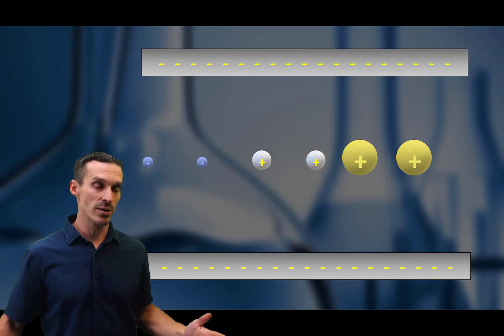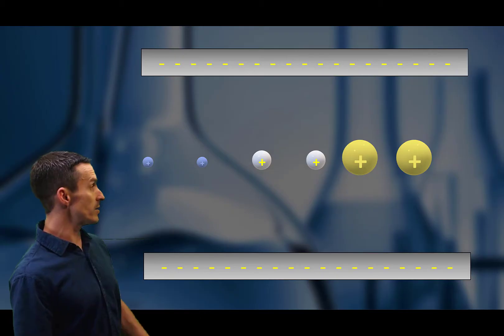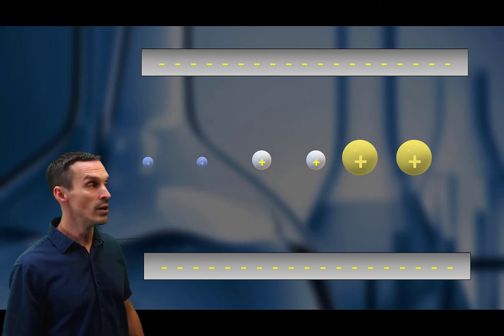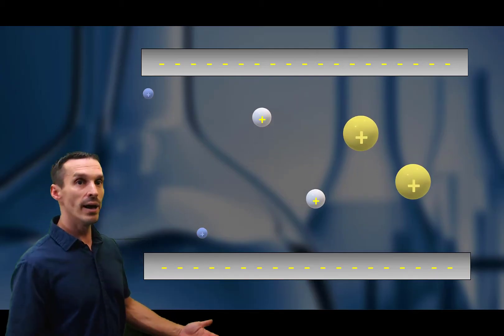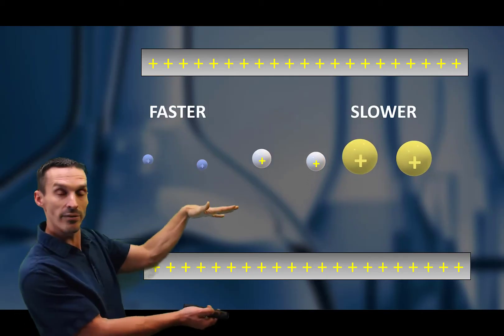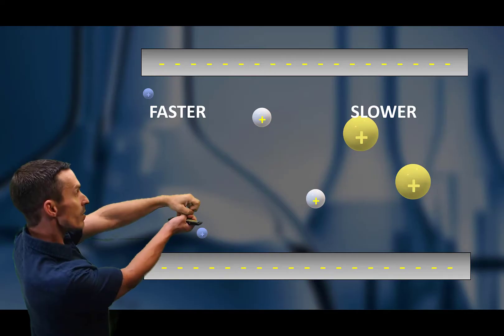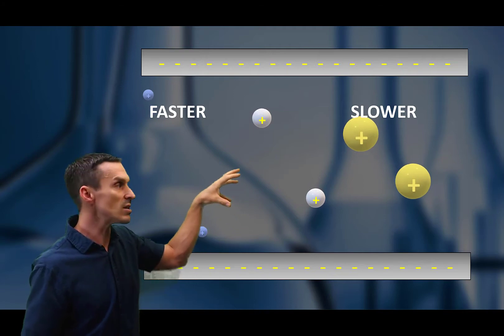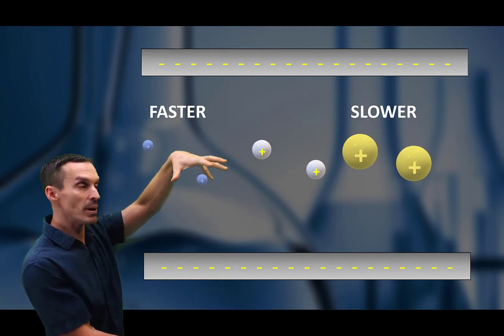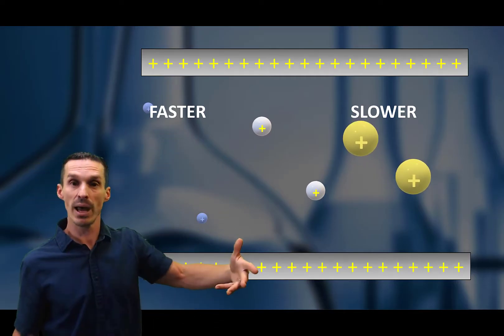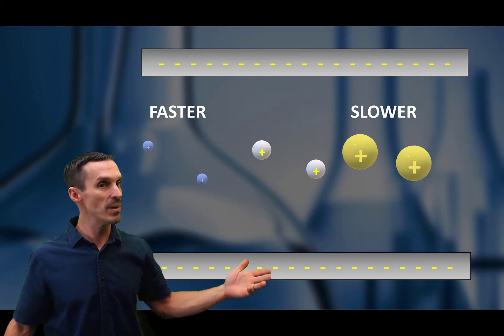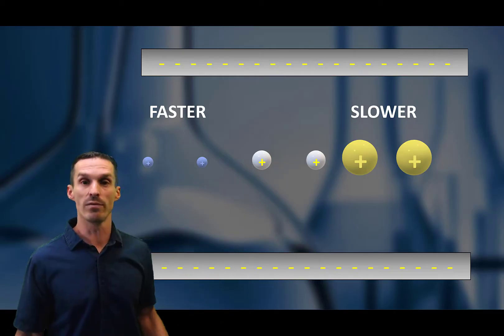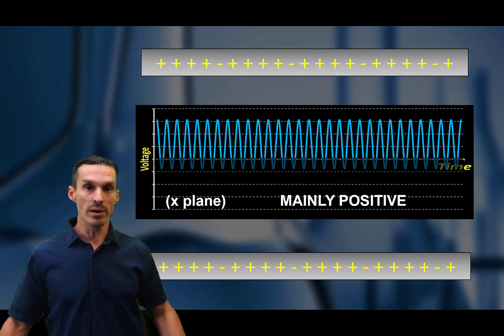This is a mass spectrometer, which means that we have ions of different mass-to-charge inside the electric field. So let's see what happens as we change the charge, the polarity of the quadrupoles for different ions. Well, there's still going to be that pull, and then the charge will reverse, and then it's going to push them back down. But what you're noticing here is that the smaller ions are moving out faster. The big ions sort of stay slow and stuck into the middle. So they're all pulsing up and down, but how big they pulse is going to depend on their mass-to-charge, and that's simply because small ions move quickly, the big ions have a lot of momentum—they're kind of sluggish, they stay put for longer.